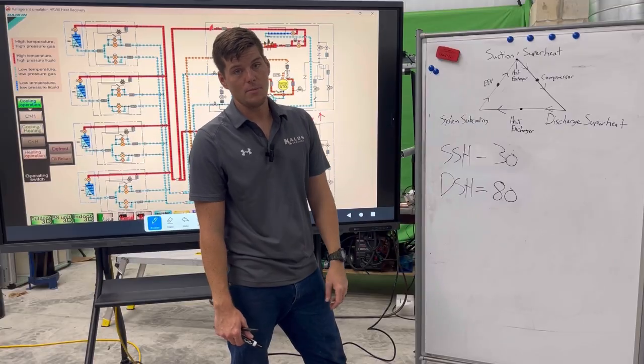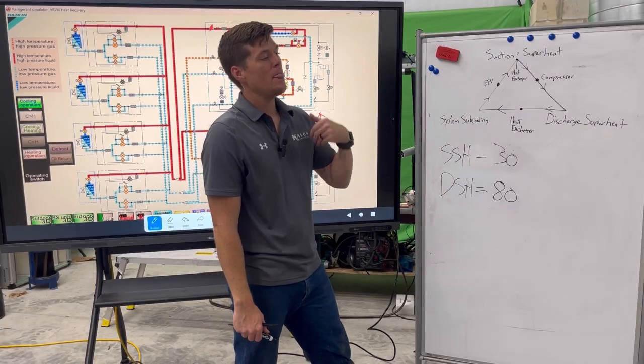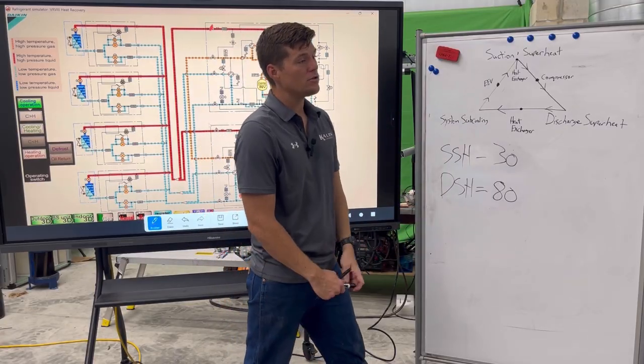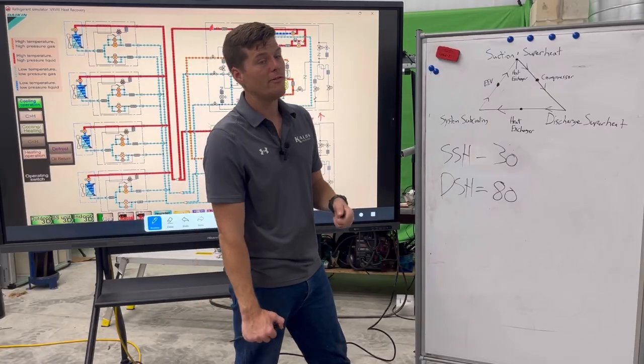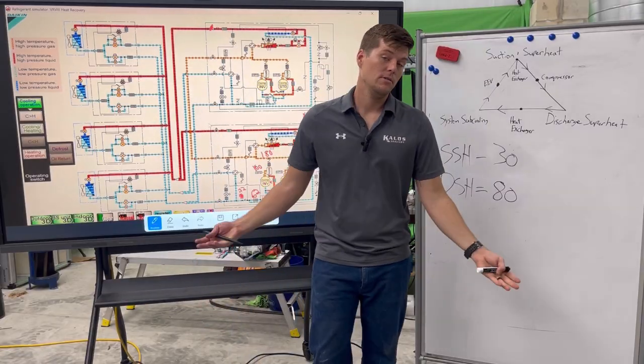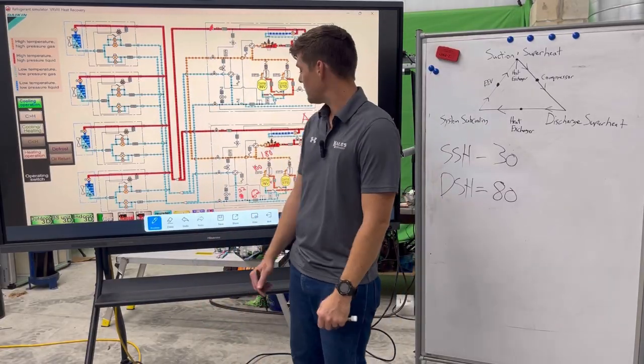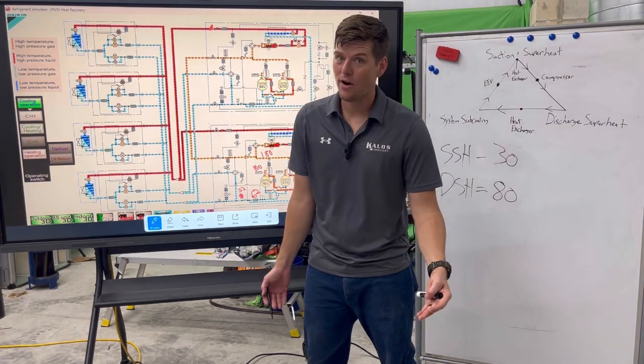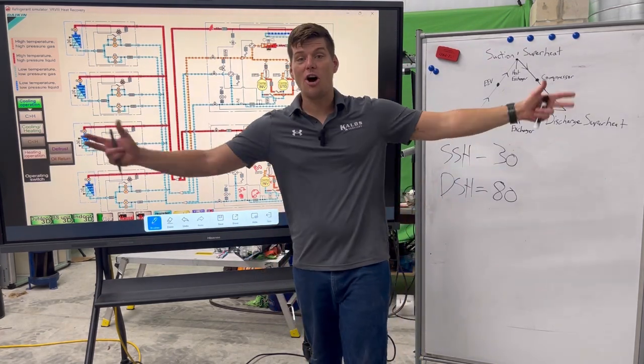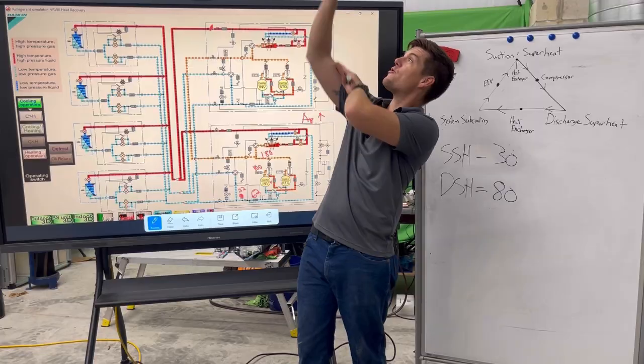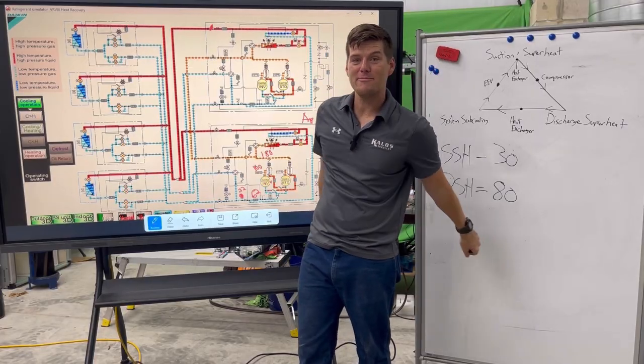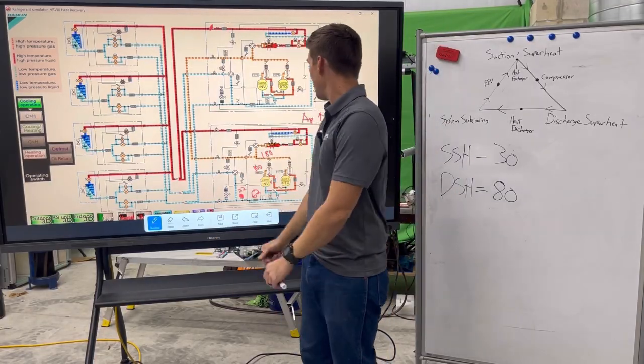Both of these things tell me that I'm not getting enough vapor to my pump. And then out the other side, I am also showing signs that I am not getting enough vapor, or both, lack of vapor and a little bit of lack of oil. Again, if it was a lot of oil, those are those compressors that you see turn on and then they go discharge temps 300 degrees in a matter of 5 minutes, right? And we've all seen it.